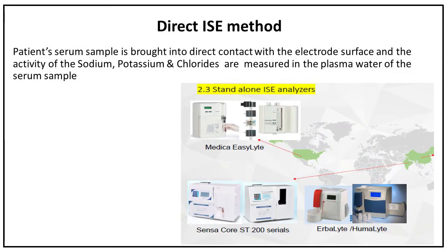With the direct ion-selective electrode method, the patient sample is brought into direct contact with the electrode surface, and the activity of sodium, potassium, and chloride are measured directly in the plasma water of the serum sample.